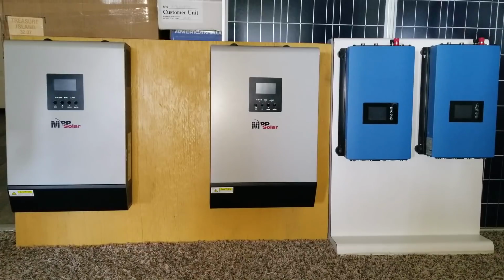If your battery is gonna be at float on a 48 volt system, it has to be at a float close to, for example, if it's a flooded acid battery, they tend to go to equalizing mode. I'm not gonna encourage or recommend you use that kind of setting for this, because the voltage is gonna be higher. It might probably work. It depends on the battery specification, or the battery parameters.